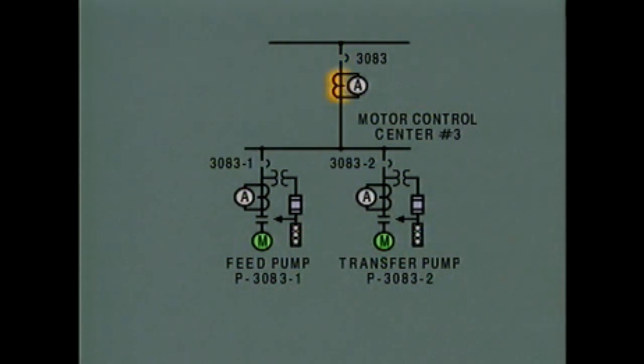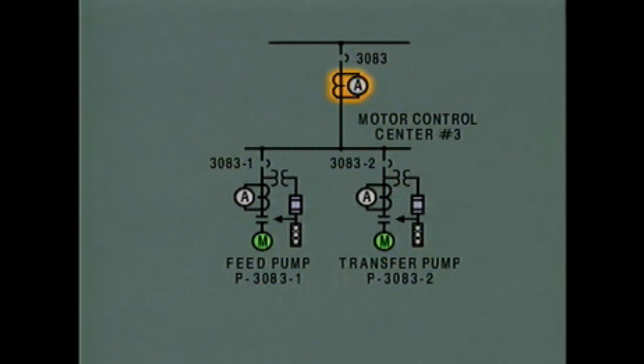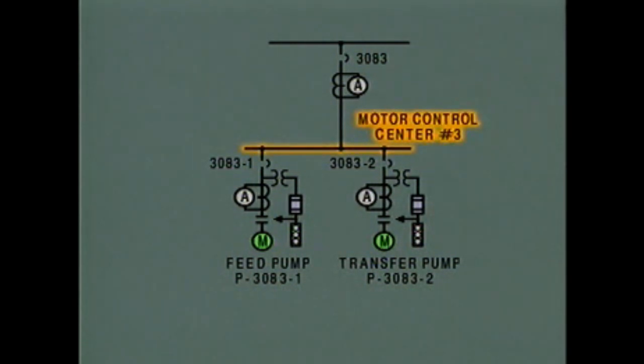From the circuit breaker, power flows through a current transformer. The current transformer produces a small current that's used by the ammeter. The ammeter provides an indication of the total current flow to the motor control center circuit.